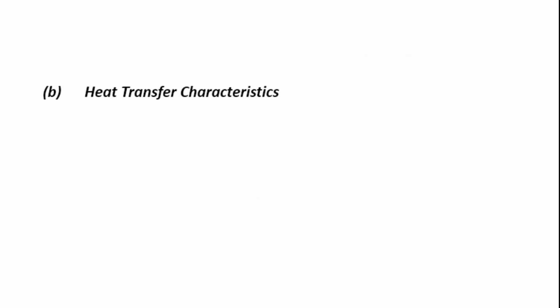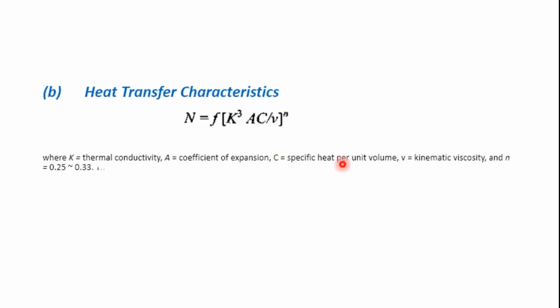Next we have the heat transfer characteristics. In equipment filled with liquid dielectric, like transformers, cables and circuit breakers, heat is transferred mainly by natural convection. Under natural atmospheric conditions, cooling convection is given by N equal to F into K to the power of 3 AC by V to the power of n, where K is the thermal conductivity, A is the coefficient of expansion, C is the specific heat per unit volume, V is the kinematic viscosity, and n varies from 0.25 to 0.33. The main factors that control the heat transfer are thermal conductivity and viscosity. We have to be wise enough to choose between conductivity and viscosity.